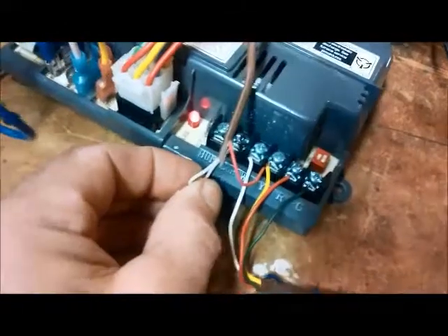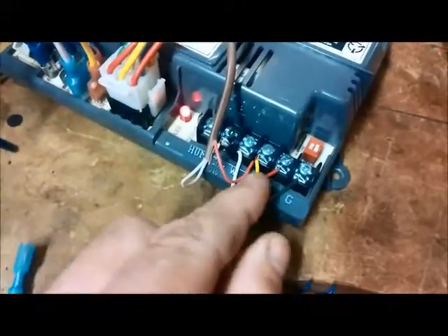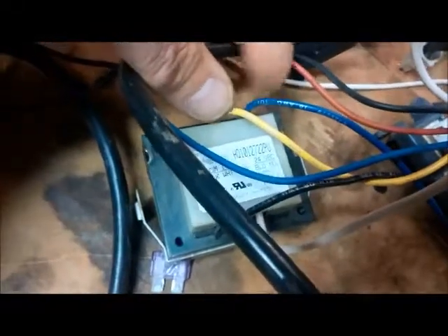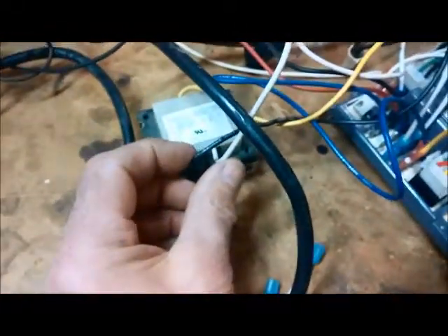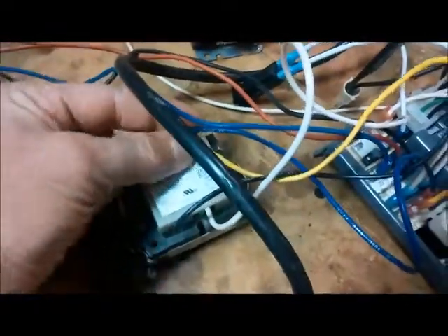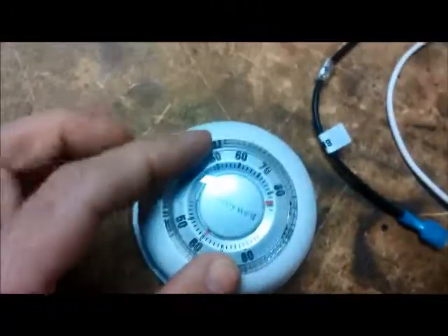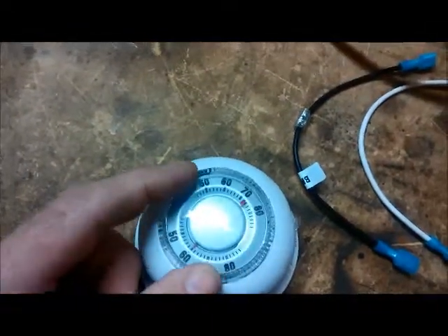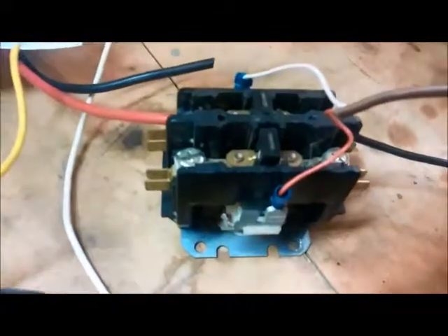Our Y, here's our wires going out to the air conditioner. We have a Y, that's our C, and our Y. 24 volts is sent out on Y, and then it comes back to the board to C, which ends up at one of these two wires. The transformer puts out 24 volts through these. 110 in here coming from the board, 24 volts coming out here, back to the board, and then ends up, basically this blue and yellow is the same as R and C on the board. So we initiate a call for cool. Once this turns down below 60, you'll see the contactor pull in.